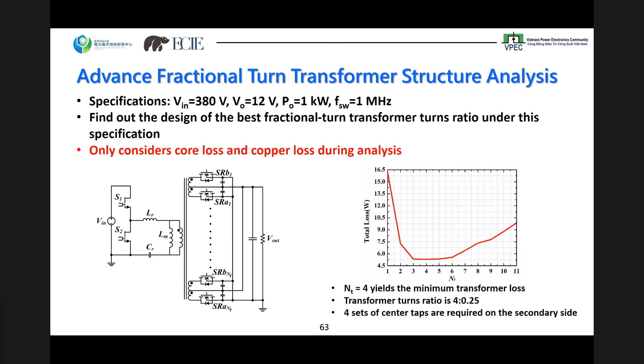The professor from Kunming proposed an idea about a half turn design, and based on that idea we designed a quarter turns transformer. As you can see, this figure shows different turns ratios, like 1/2, 1/3, and 1/4 turns. Comparing the total loss under the same conditions, the 1/4, the quarter turns, gets the best performance, with lower total loss. Okay, so here is the specification and the turns ratio. The actual turns ratio is 4 to 0.25.